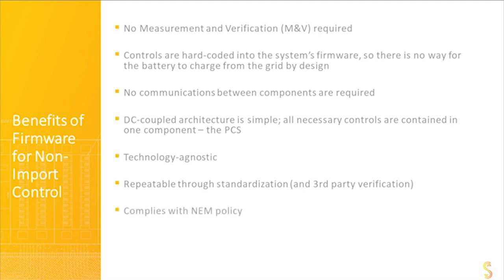All of this was designed to comply with NEM policy, which is really important. This is how we allow batteries to export into the grid and reap NEM credits for it, actually get paid for it. I mean, that's really incredible. Basically, it could be in the middle of the night, at midnight, and the utility will suddenly see an export from our DC coupled solar plus storage system and allocate NEM credits in the middle of the night. That's never been done before. And if that's the right time to discharge the battery based on tariff rates or whatever rate pricing structure we're in, we're literally making the sun shine at night. And we're doing it in a perfectly NEM compliant fashion.